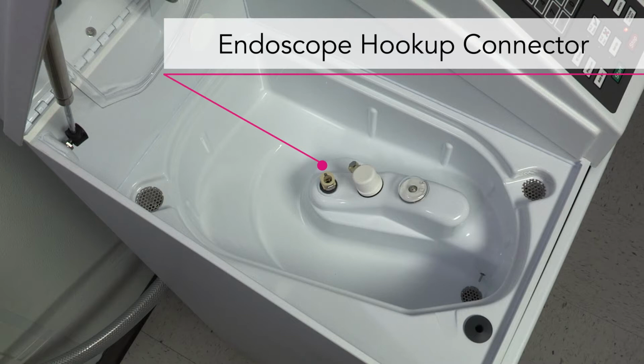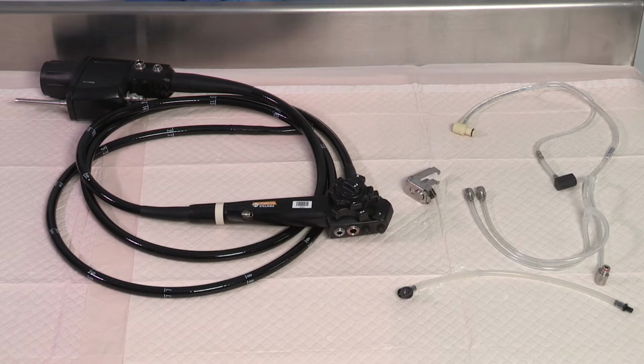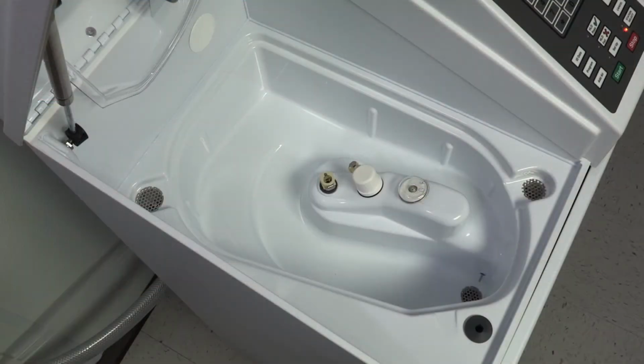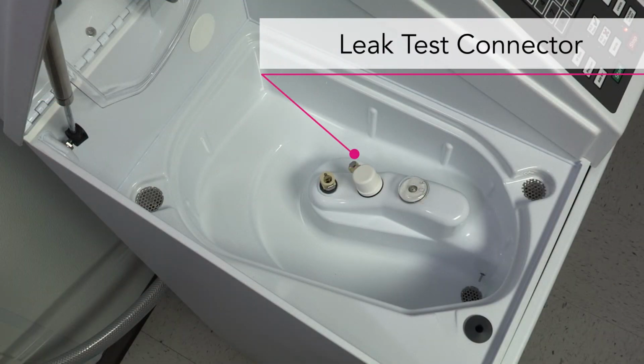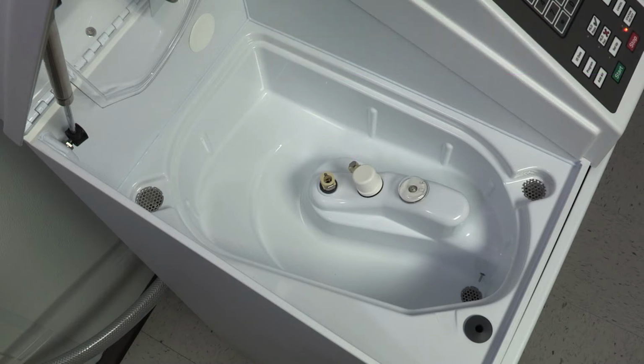The Endoscope Hookup connector attaches the hookup to the DSD EDGE Reprocessor. Hookups are the interface between the DSD EDGE Reprocessor and the endoscope. They deliver correct flow rates that meet manufacturer specifications. The Endoscope Leak Test connector connects to the DSD Leak Test hookup, which attaches to the leak test port on the endoscope. Automated leak testing continues throughout the cycle when an endoscope is connected to a DSD leak test hookup.